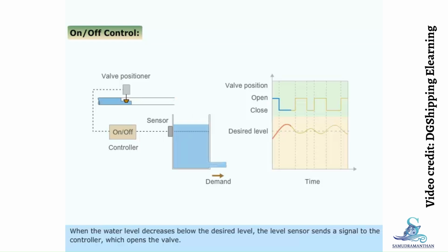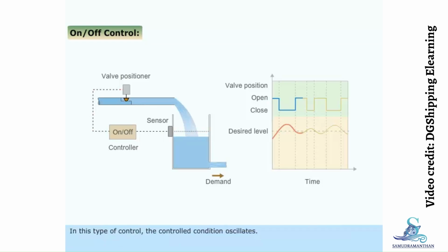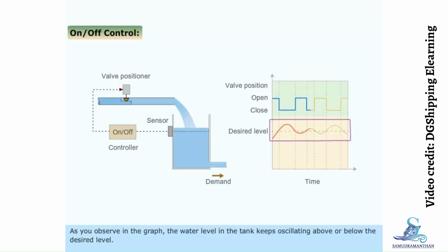When the water level decreases below the desired level, the level sensor sends a signal to the controller which opens the valve. In this type of control, the controlled condition oscillates. As you observe in the graph, the water level in the tank keeps oscillating above or below the desired level.